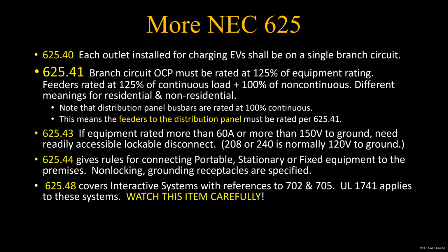625.44, all right, and again, here's the one that's interesting, 625.48. This is where the code anticipates that interactive systems means that your charger is going to interact with the utility, and it can send power back to the utility if requested. And if that's the case, then you have to refer to NEC 702 and 705. And 705 is the interconnection of a renewable power source to the utility. And it says you have to have good sine waves, have to properly synchronize. It's the UL 1741 thing. And so any system that has a UL 1741 rating means it is capable of selling back to the grid as well as purchasing from the grid.